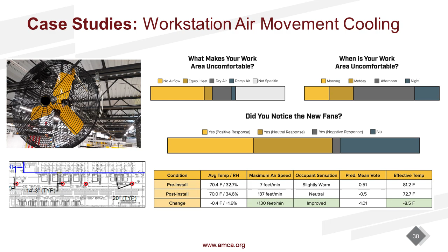When we originally presented this data, the customer was kind of alarmed that a large percentage of associates did not notice the new fans. To me that was really good, because we put them up out of the way, not causing disruptive airflows or blowing papers around. We still asked these same associates about their comfort, so whether they did or didn't notice the fans is fine by me, as long as they're actively or passively aware that conditions are better. It was mission accomplished as far as I'm concerned.